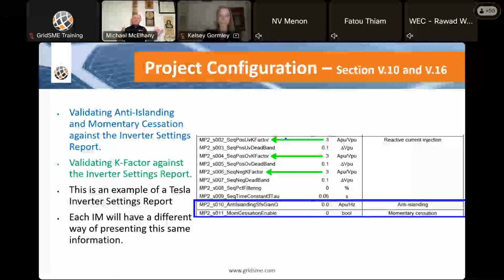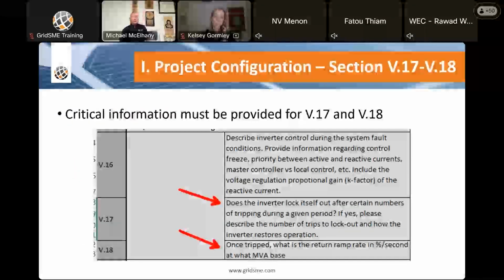But there is a question that says, is anti-islanding disabled or not, in Attachment A, which is neutral to whoever the inverter manufacturer is. But we also have to make sure that the settings document, the inverter settings report, has the same thing. And this particular one is a Tesla example. It's showing a K factor, a positive K factor, a negative K factor of 3. That again needs to line up with V.16 within the Attachment A workbook.